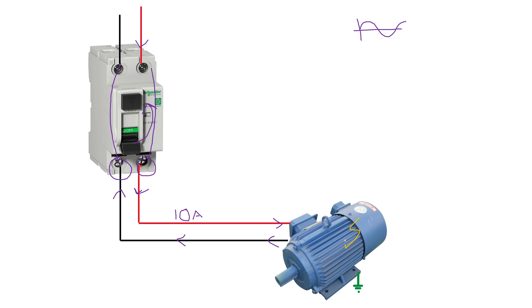If, say for example, this motor develops a fault inside — maybe some of the insulation breaks down and some of the current makes its way to earth — that means that less current will be returning. So say for example, we had a steady state current of 10 amps and now only 9 amps is returning. At that time instant, we will find that there's an imbalance and this earth leakage or this RCD will then trip, disconnecting the current because of that imbalance. And that's one of the reasons why it's called an earth leakage because the current most of the time is leaking to the earth.